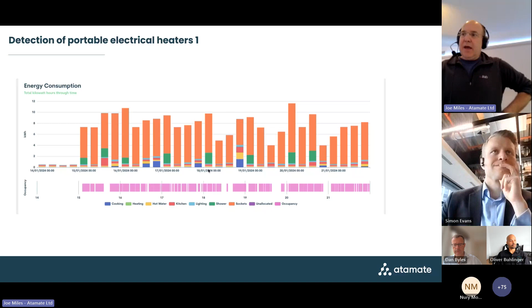If we compare that to the energy use in the building, in this time series data you can see quite clearly that we're exceeding our set point. The temperatures in that room are exceeding the set point, and at the same time the heating's not being turned on and off in those spaces. That means the only way you can be reaching those temperatures is a secondary use of heating, so we're very confident that in this room they're plugging in portable electric heaters, and the problems associated with those.